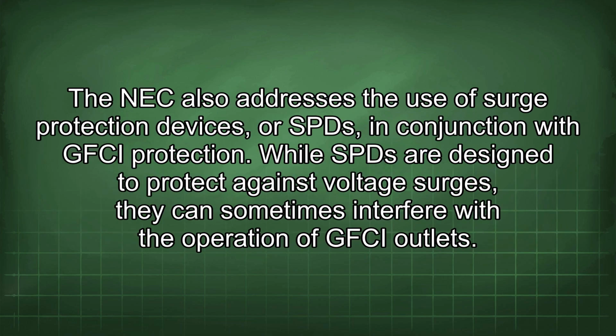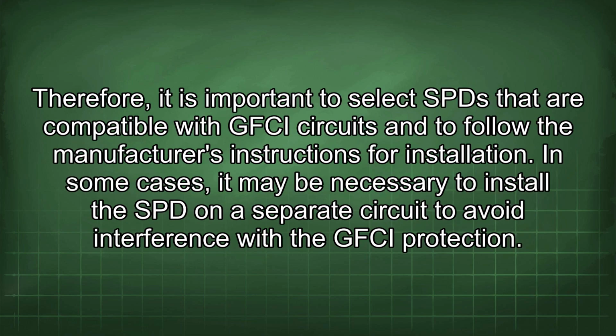The NEC also addresses the use of surge protection devices, or SPDs, in conjunction with GFCI protection. While SPDs are designed to protect against voltage surges, they can sometimes interfere with the operation of GFCI outlets. Therefore, it is important to select SPDs that are compatible with GFCI circuits and to follow the manufacturer's instructions for installation.